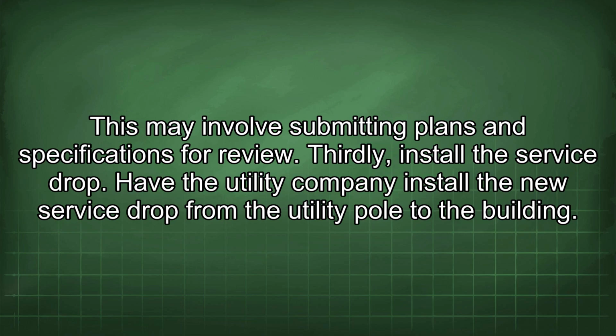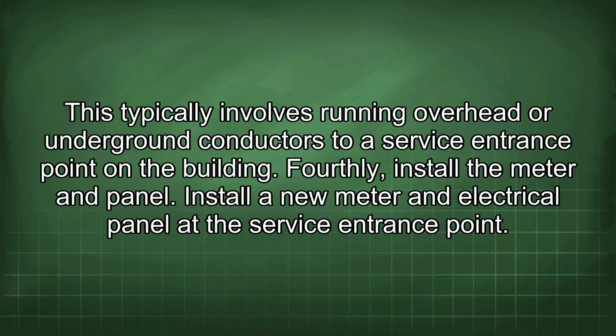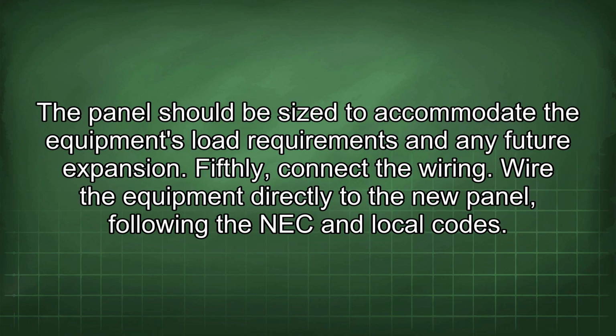Thirdly, install the service drop. Have the utility company install the new service drop from the utility pole to the building. This typically involves running overhead or underground conductors to a service entrance point on the building. Fourthly, install the meter and panel. Install a new meter and electrical panel at the service entrance point. The panel should be sized to accommodate the equipment's load requirements and any future expansion.